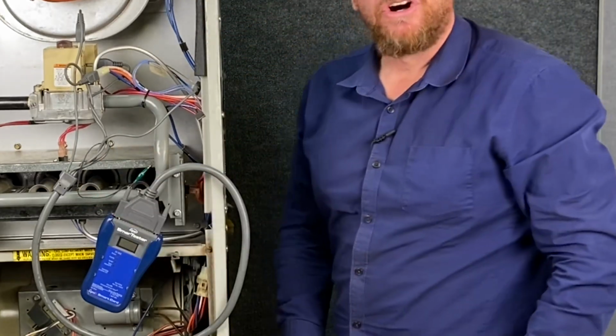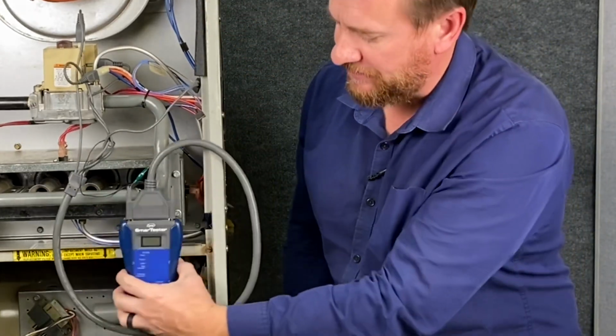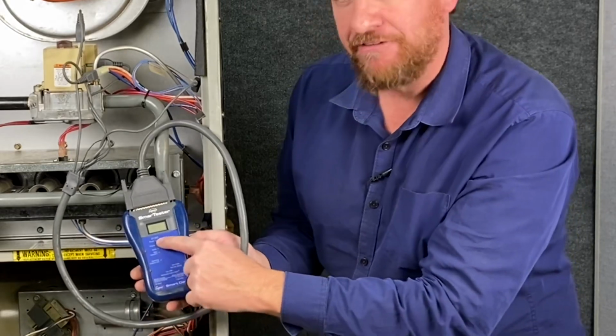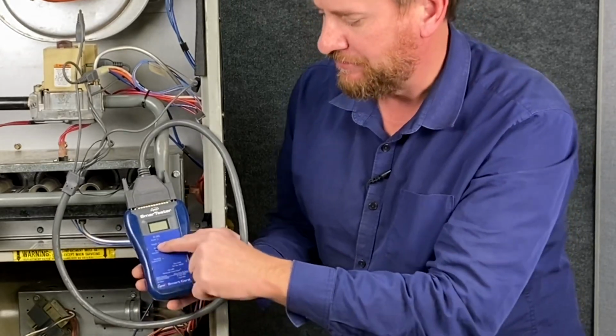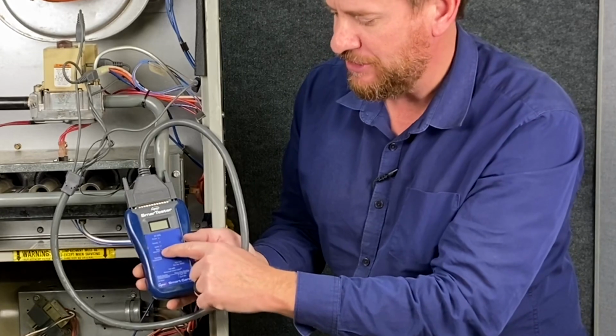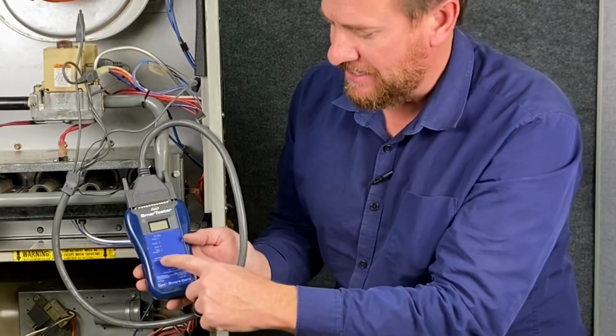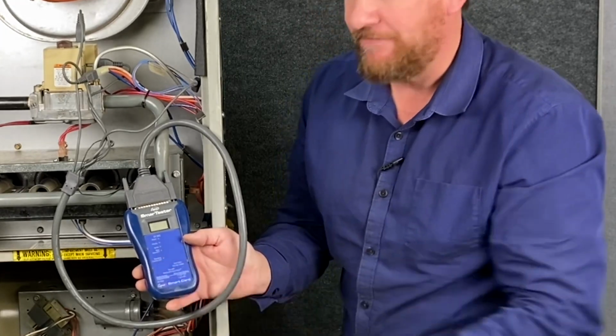Now we're ready to have a call for heat, so we can actually go through the process, and this cord is going to tell us if we have 24 volt power. It's going to tell us if we have the correct polarity, if we have ignition, if our main valve ignites, and if we have our main fan motor running.